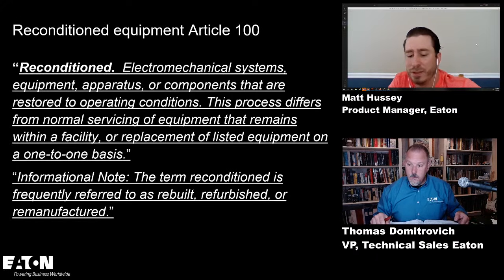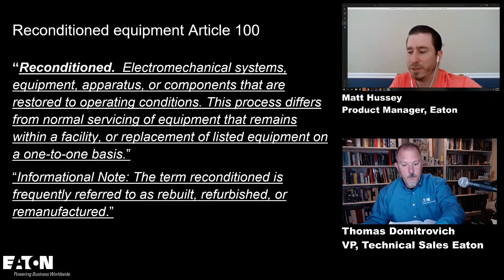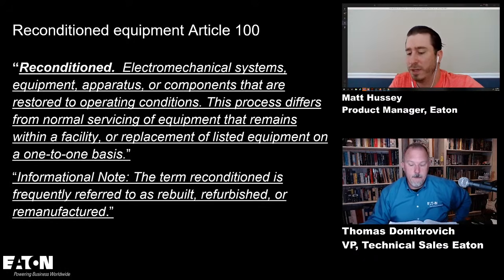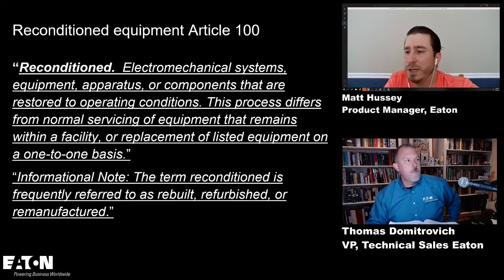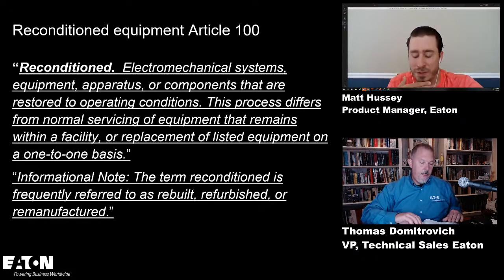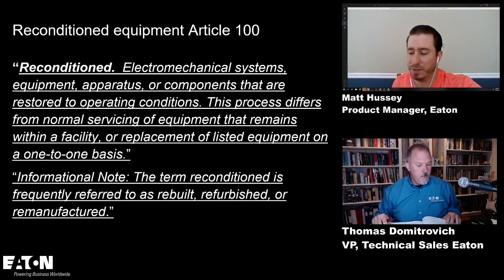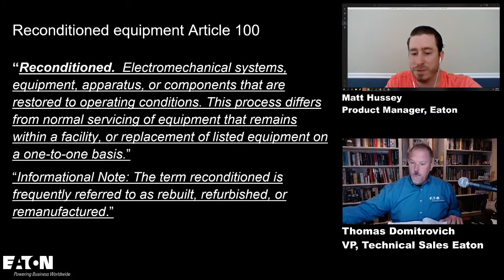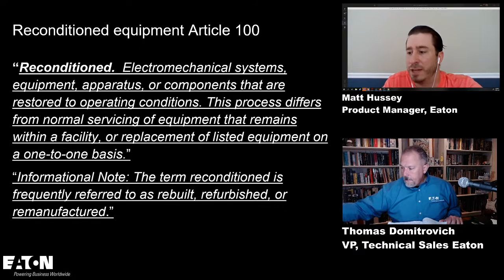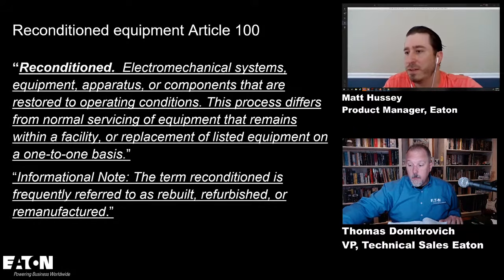Yeah, I think the dialogue that I've heard is that there's concern over extent. So if a door has been bent and you want to get a replacement door, is that considered normal servicing or is that restoring it back to operating conditions? And then obviously there's a lot of concern if the damage you're trying to repair the equipment from is a result of a short circuit event or something like that. How do you know that the rest of the integrity of the equipment is still intact? So, good point.